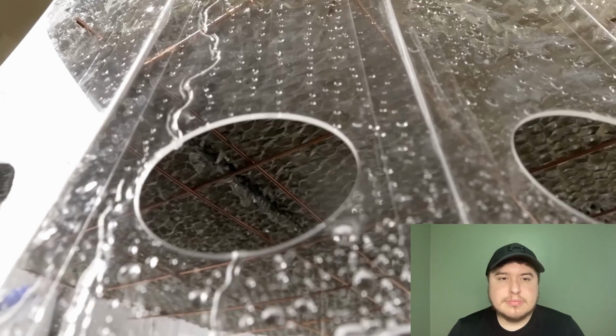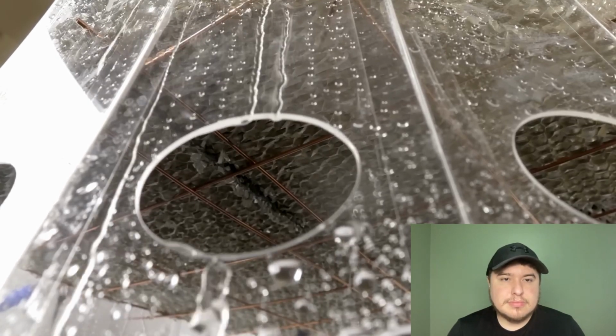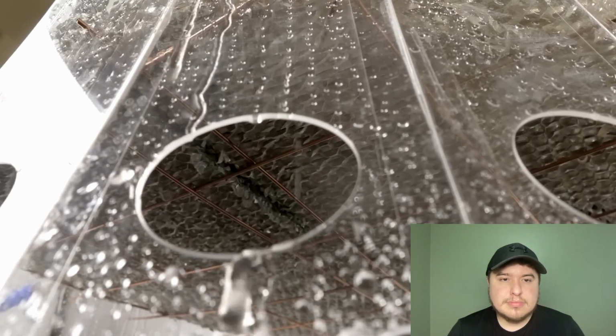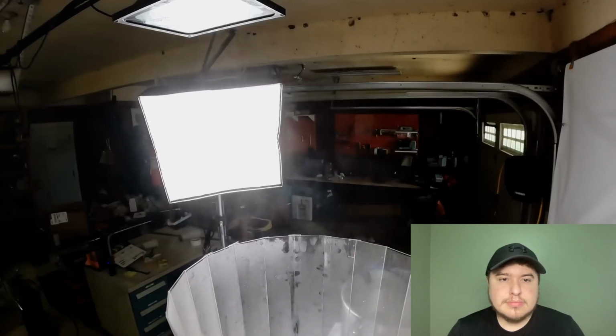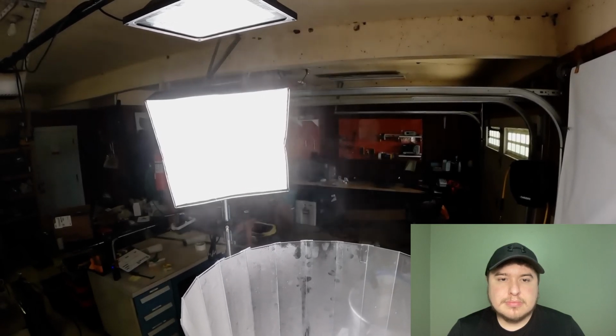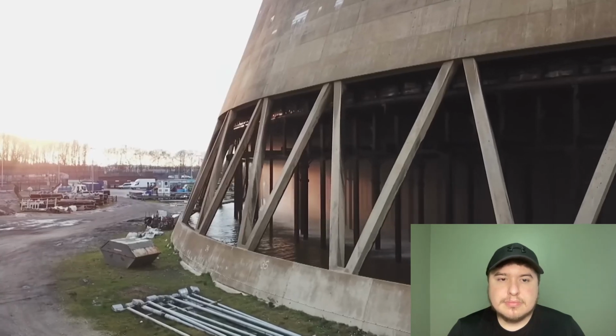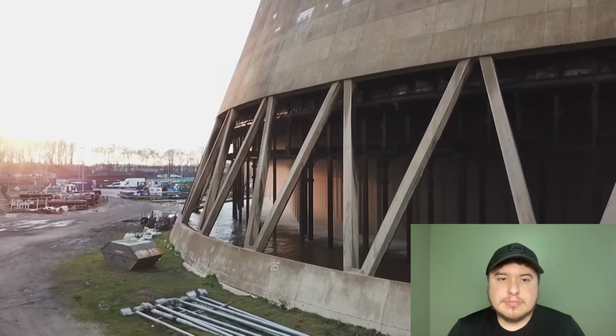And this is the second key to a cooling tower: convection. The hot water transfers its heat to the air, the warm air becomes buoyant, flowing upward in the tower and drawing fresh air in through the intakes. But some of that hot water is also evaporated, removing more heat from the water and making the air even more buoyant. The process both cools the water down and creates a natural draft up through the tower, drawing in even more fresh, drier air as it does. Ignoring the pumps and minor control features, there are no moving parts.